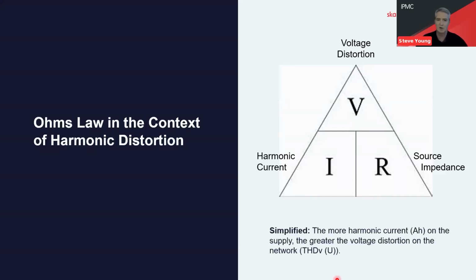And wherever we've got high current distortion and we've got ultimately considerations for voltage distortion, we can look at that in the context of Ohm's law. So if we think of V being the voltage distortion, the product of high current distortion, V is I times R, if you like. So across a fixed impedance of a source, if we increase the harmonic current, then we're going to increase the voltage distortion. So simplified, the more harmonic current on the supply, the greater the voltage distortion on the network. And that's going to be seen everywhere on that low voltage network.